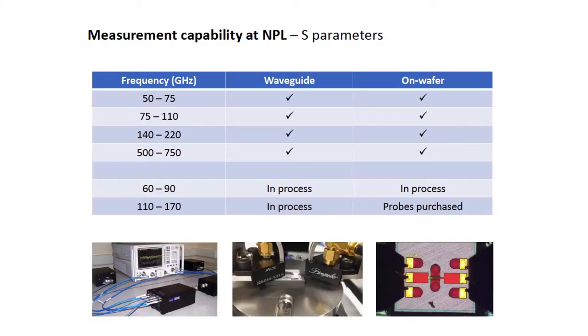Next I want to talk about some recent research activities at NPL. Before that, I want to show our measurement capability at NPL for S-parameters. We have very good capability below 50 GHz; in this table I only show our measurement capability at millimeter-wave frequencies. Above 50 GHz, we have coverage for waveguide bands: 50–75 GHz, 75–110 GHz, 140–220 GHz, up to 500–750 GHz. We have on-wafer probes for all these waveguide bands. By the end of this year we are also going to acquire a pair of E-band extender heads to have measurement capability for E-band.